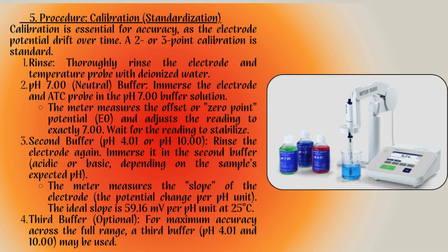Calibration is the most crucial step for accurate pH measurement because the electrode's potential naturally drifts over time. We perform a 2 or 3 point calibration using certified pH buffer solutions. Step 1 is rinse. We always start by thoroughly rinsing the electrode and the ATC probe with deionized water to prevent cross-contamination. Step 2 is neutral buffer. We immerse the probe in the pH 7 buffer.